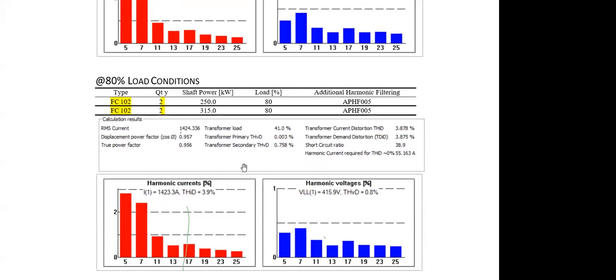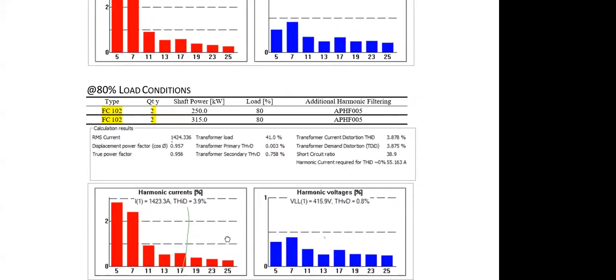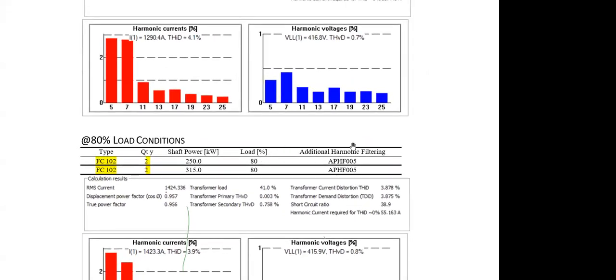Why I brought this up again is that it is important when we are getting equipment, I mean a VFD. Each and every VFD has harmonics, no doubt about it, because of its working principle. It is not a bad product, or the supplier trying to fool us. It is not like that. It is because of its working principle, its working philosophy. It has to create harmonics. It cannot prevent it.